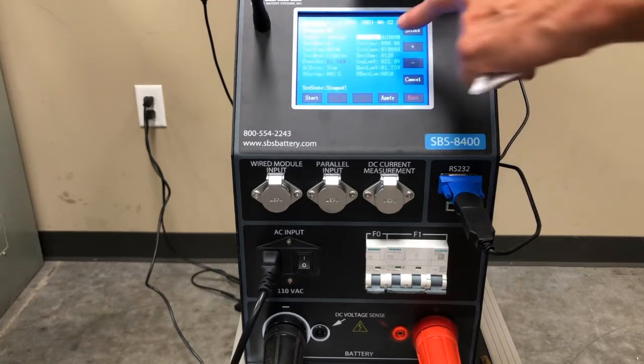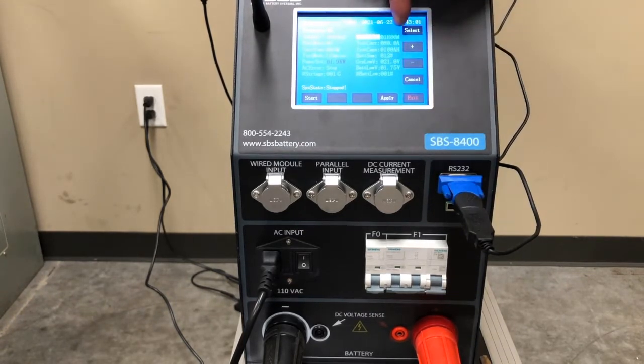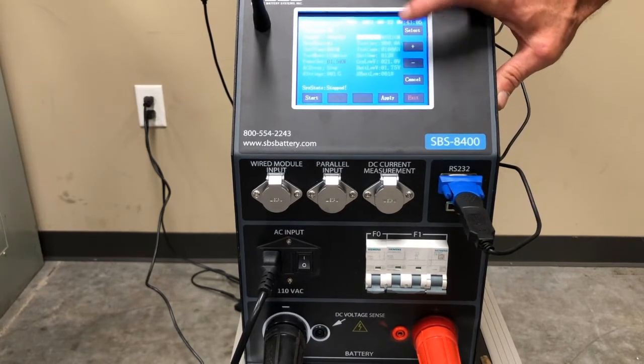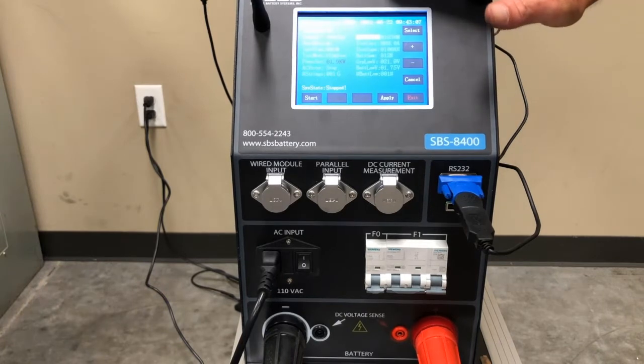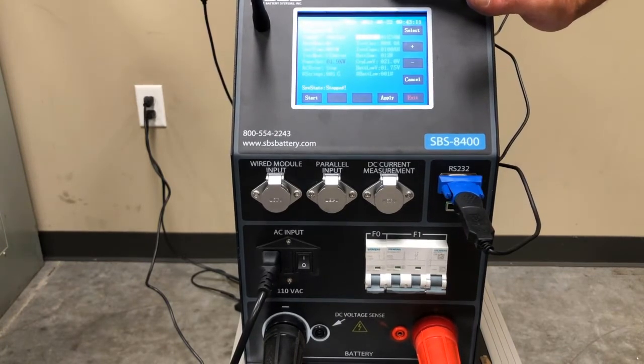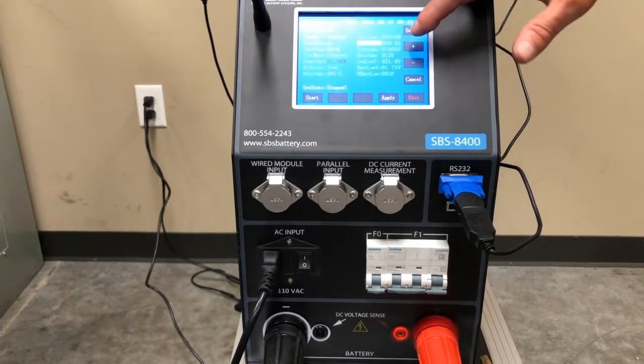So test time, this is a shutdown parameter. So I'm running a 1-hour test, but I want to program this test to 1 hour and 30 minutes so that if the battery's more than 100% capacity, I let the load bank run long enough to capture what the true capacity is. My test current, I pulled that off the data sheet. That was 97.3 amps.